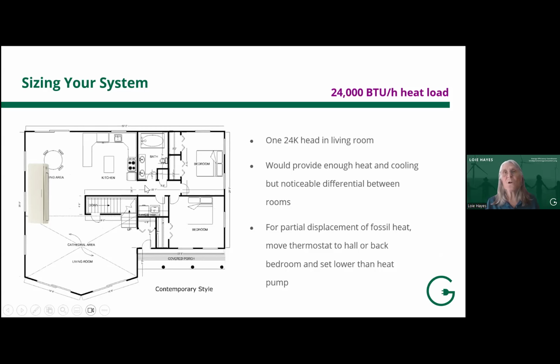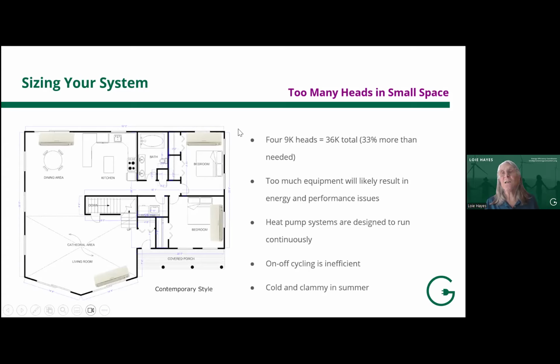That's one option. What we want to warn you against is when you have a heat load of 24,000 BTUs and a contractor comes in and says, oh, I'll stick a 9,000 BTU head in each of these rooms in order to have perfect temperature control in every room. The problem is that gives you a total capacity of 36,000 BTUs. It's way more equipment than you need. And the problem with too much equipment is that it will come up to temperature quickly, and then it will have to shut off because it can't get any further in that direction without making you uncomfortable. And then temperature will come down and it will have to come on again. Heat pumps are designed to work continuously like a flywheel for greatest efficiency. And when they turn on is when they're using a lot of energy to come up to temperature. So a system that is oversized will modulate too much and be too expensive to run.